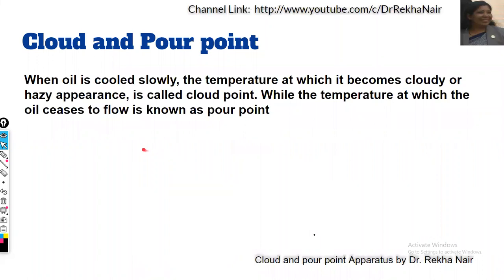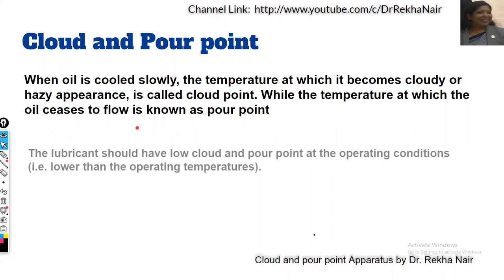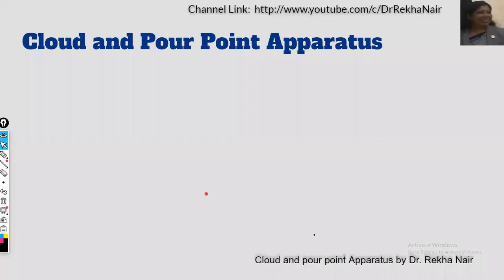When oil is cooled slowly, there is a temperature at which it becomes cloudy with a hazy appearance — we call it the cloud point. The temperature at which the oil ceases to flow is called the pour point. The lubricant should have a low cloud and pour point at the operating conditions.